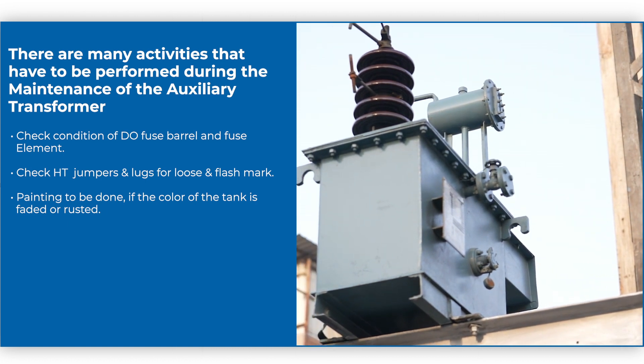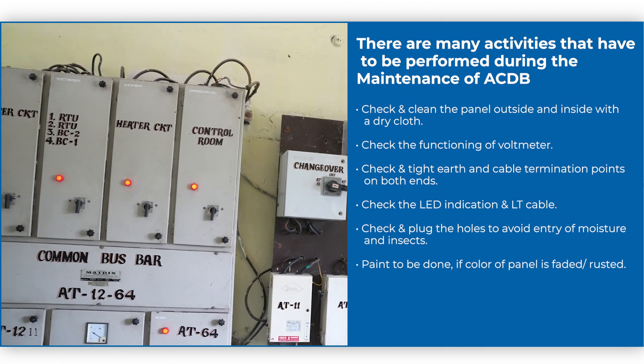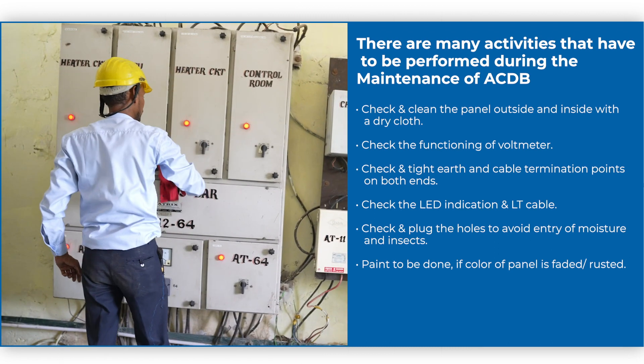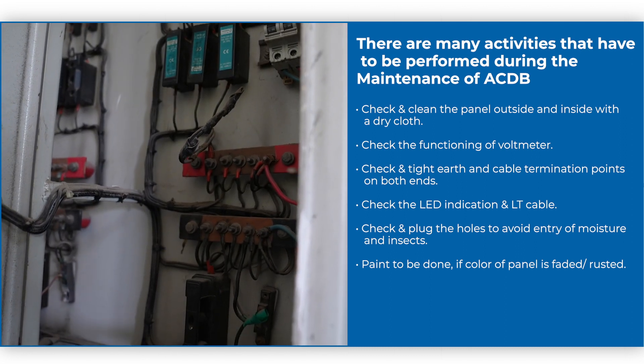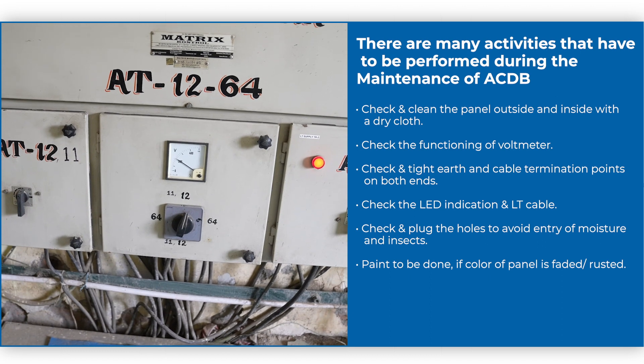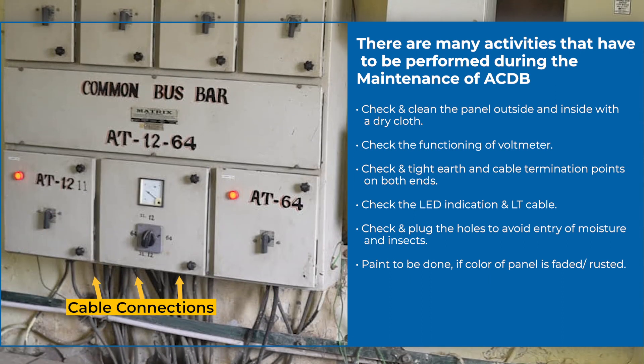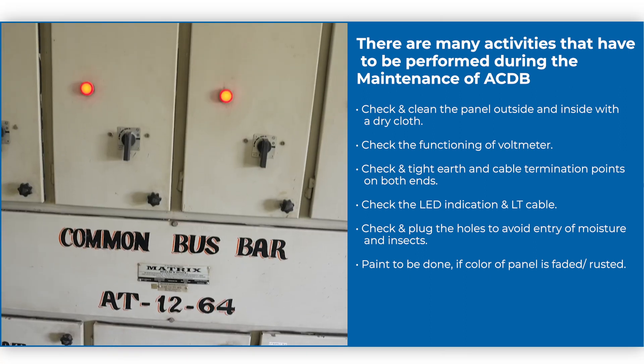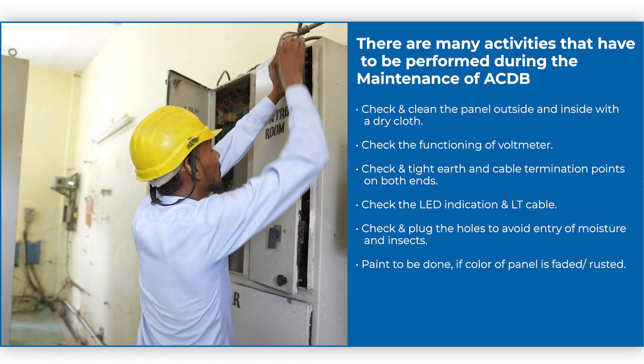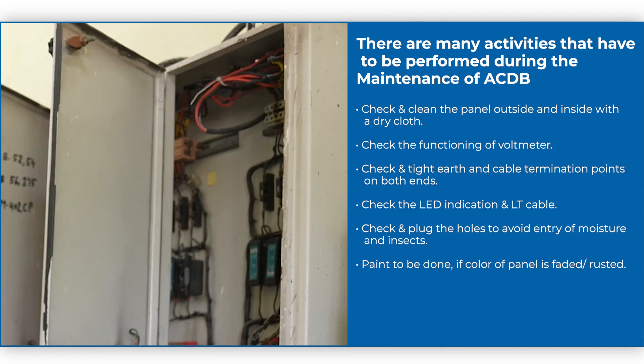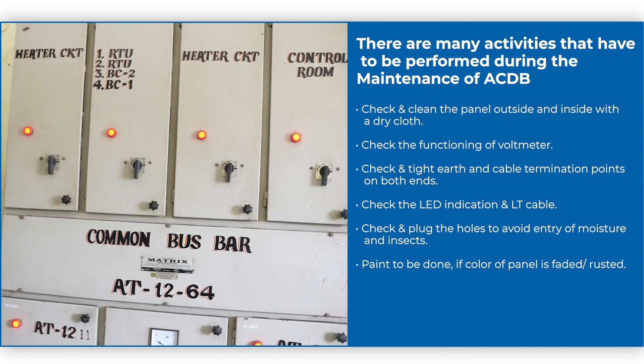There are many activities to be performed during the maintenance of ACDB. Check and clean the panel outside and inside with a dry cloth. Check the functioning of voltmeter. Check and tighten earth and cable termination points on both ends. Check the LED indication and LT cable. Check and plug the holes to avoid entry of moisture and insects. Paint to be done if color of panel is faded or rusty.